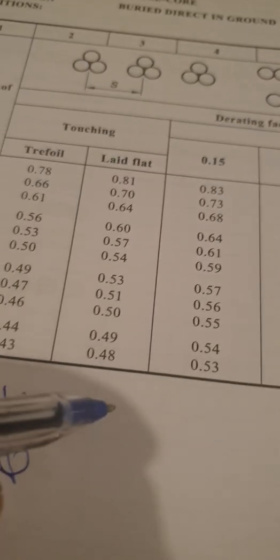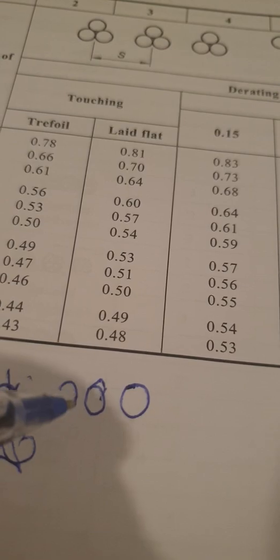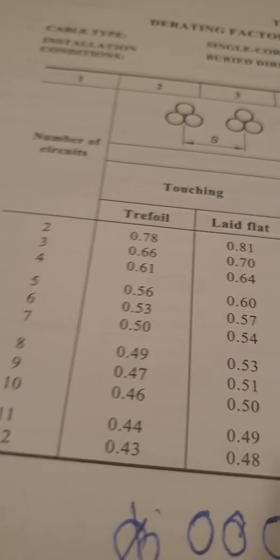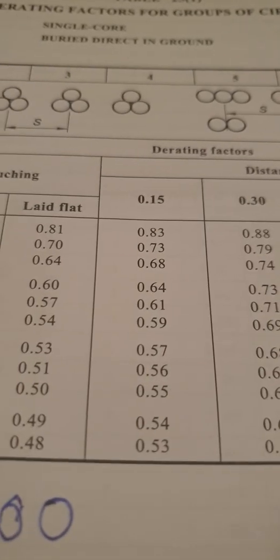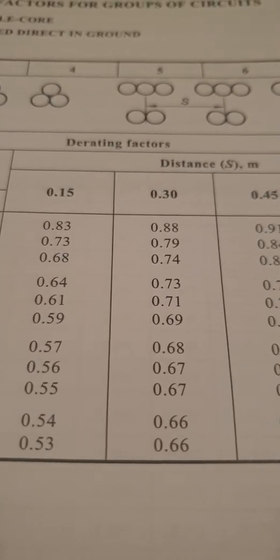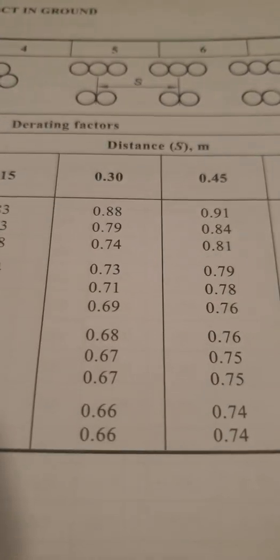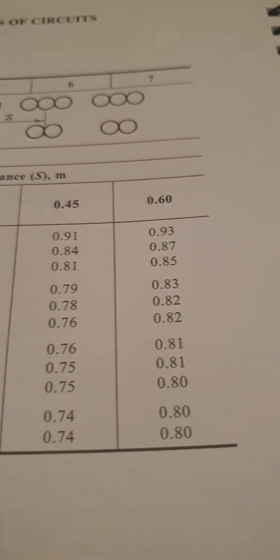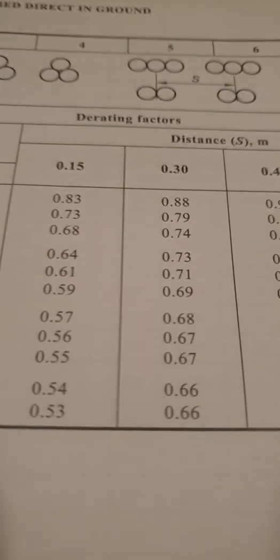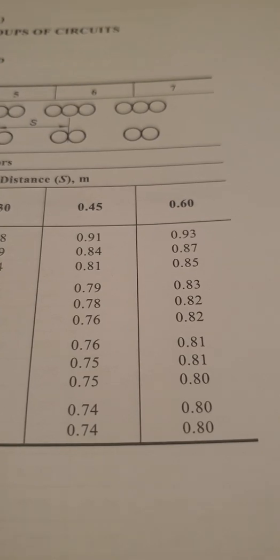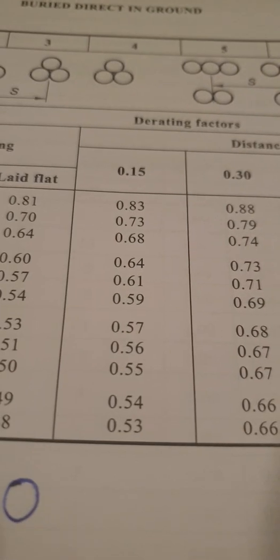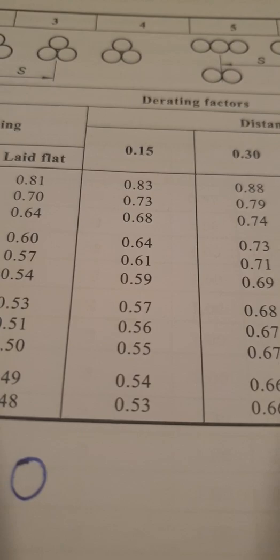Two circuits - there's a difference between them: 0.78 and then laying flat 0.81. Then we get to the distance: 0.85. So distance apart - if the cables are laying 0.15, 0.3, and then we go through from 150mm, 450mm, 600mm, 300mm. So as they get further apart, the percentage climbs up, which means you're going to get more out of it. The more closer they are together, the percentage goes down. So look at the 0.83 as a percentage value.